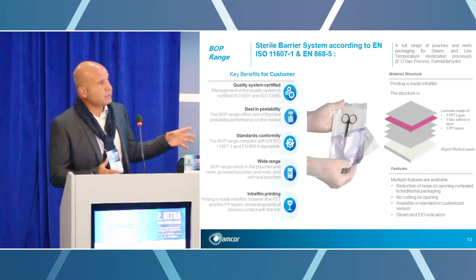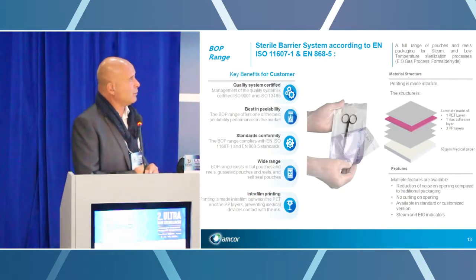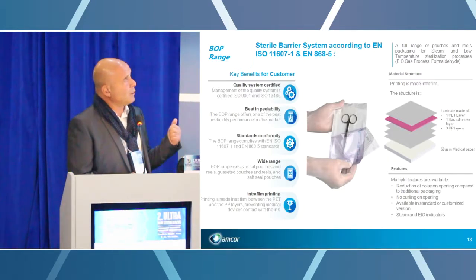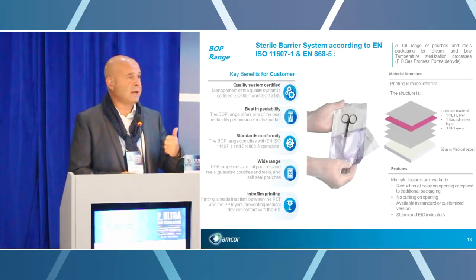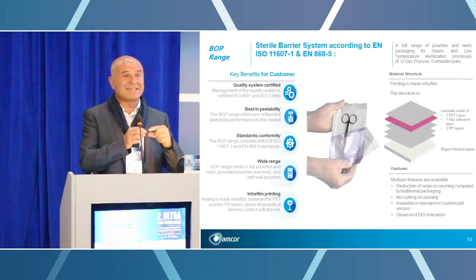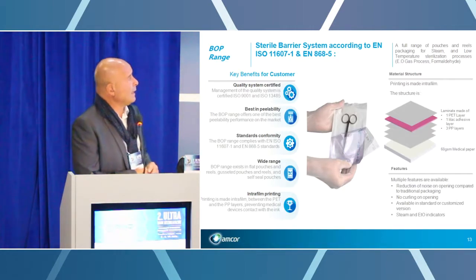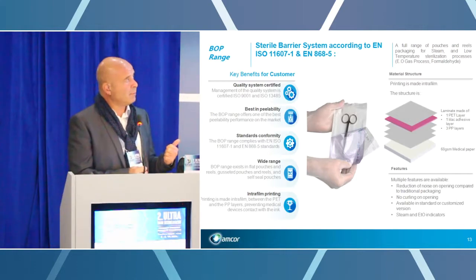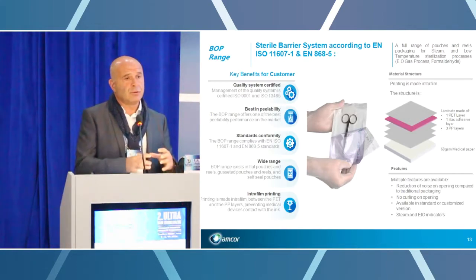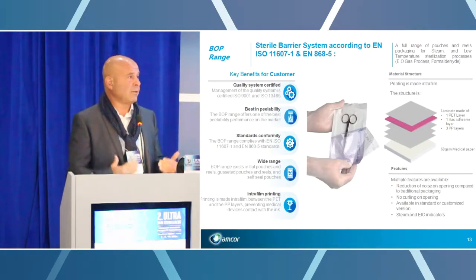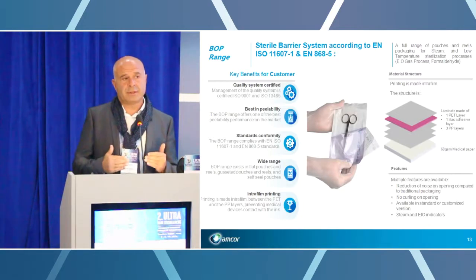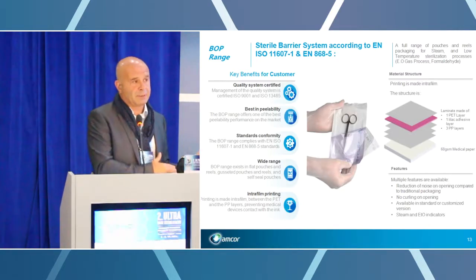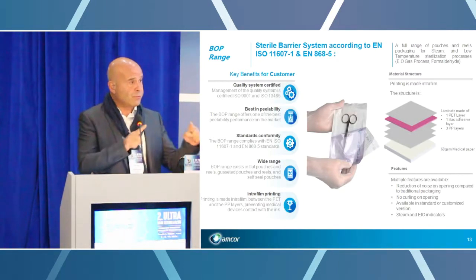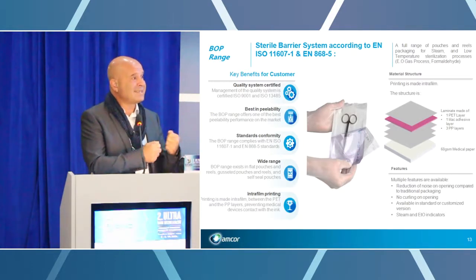This is some important characteristic of the pouch and reels. You have the color of the film, because it's better to see if your seal is good or not. For the pouch, the very important thing for the peelability is the chevron. Chevron is very important if you want to peel. It's the reason we always say, if you have the possibility to use a pouch, it's better than reels, because with a pouch you have a chevron, and with a chevron, it's very easy to peel.